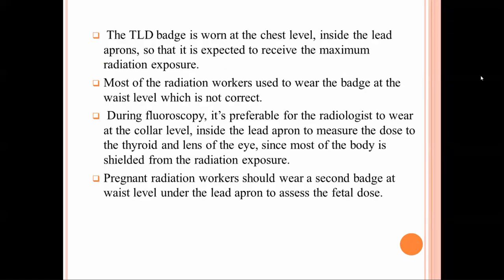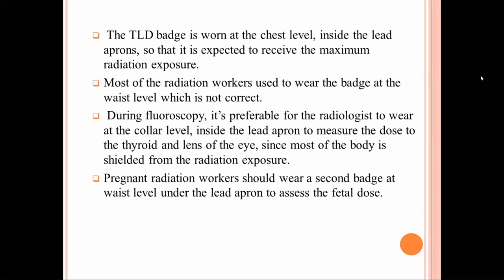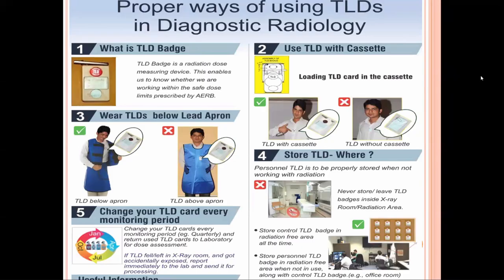Important points about TLD usage: the TLD should be worn at chest level inside the lead apron, where it is expected to receive maximum exposure. Pregnant women should wear the TLD badge at waist level under the lead apron facing the radiation source. The TLD badge should be worn below the lead apron, not above it — wearing it above is incorrect procedure. The TLD card should be changed each quarter.